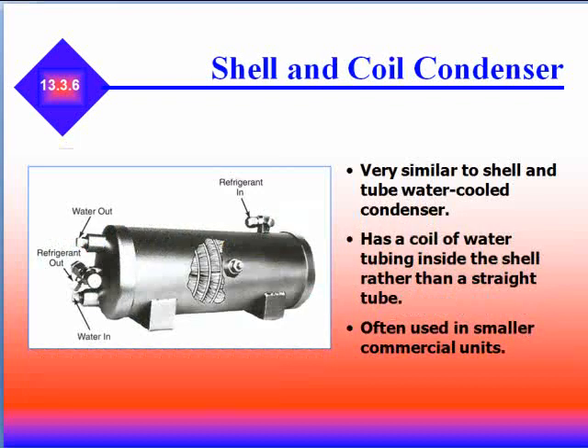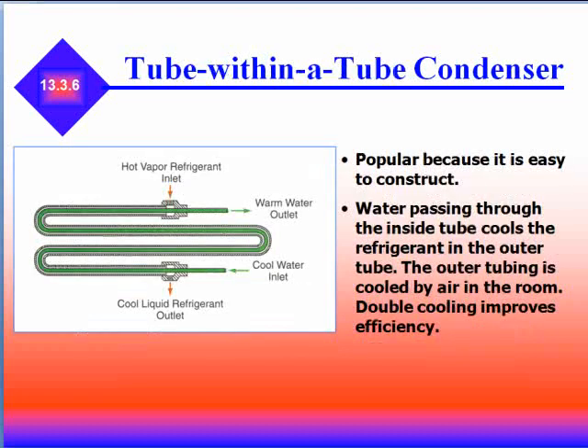The shell and coil is very similar to the shell and tube. The water-cooled condenser has a coil of water tubing inside the shell rather than straight tubes, and is often used in smaller commercial units. It's popular because it's easy to construct. Water passes through the inside of the tubes, cooling the refrigerant in the outer tube, and the outer tube is also cooled by air in the room, providing double cooling and improved efficiency.